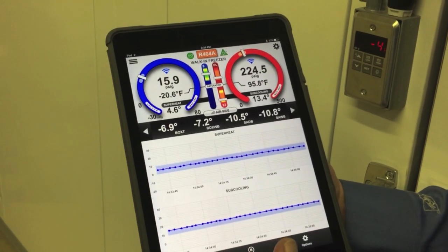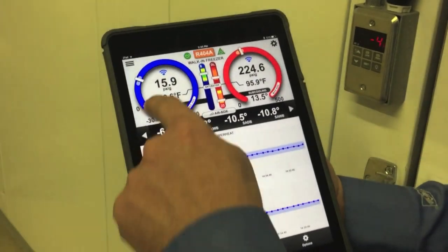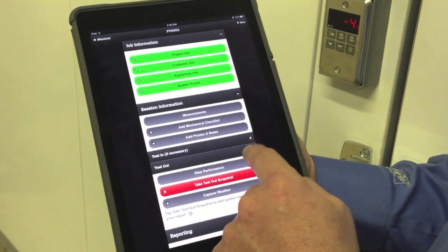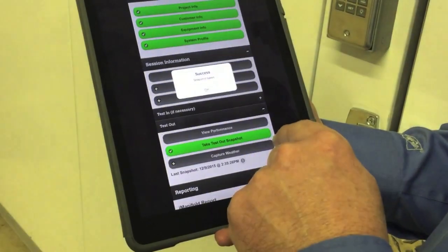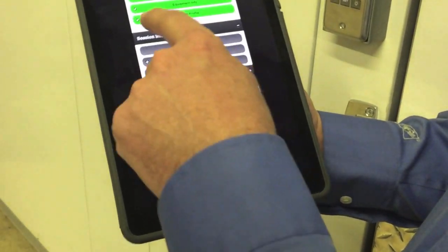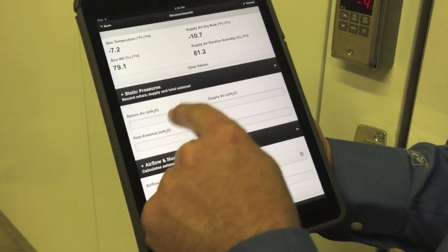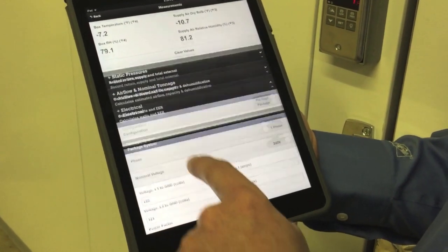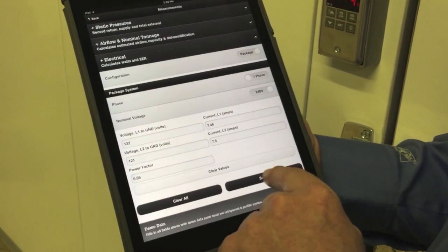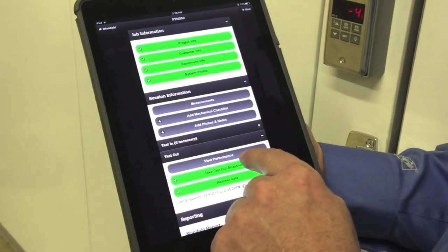We're just about ready to satisfy the box temperature. We might want to pull this information off for a report. I'm going to go back into reporting, session information, and open up the session information. I want to take a snapshot of the equipment performance — I'll take a snapshot and that's gathered. I can also capture active weather data from a local weather station for use in some of our advanced reports. We can also review our measurements — pressures, temperatures, evaporator data. We don't need static on the refrigeration system, but it allows us to pull this in. You can see our voltages, volts and amps of the system running.